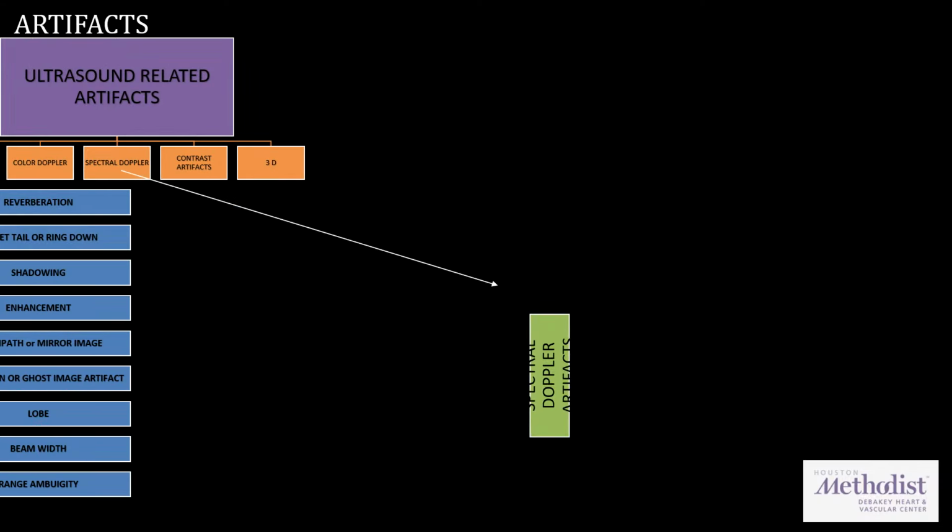The next one. Do we see all this on color and Doppler, guys? Actually, yes. Unfortunately, we see whatever we saw on color on Doppler as well. This one, look at this, guys. The first versus second image, it's the exact same one. Imagine you have the spectral gain low versus high, you're going to see that. And this one is the optimal one. Imagine you're trying to measure the peak velocity and you have the gains all over the place. Obviously, it's going to affect the peak velocity measurement.